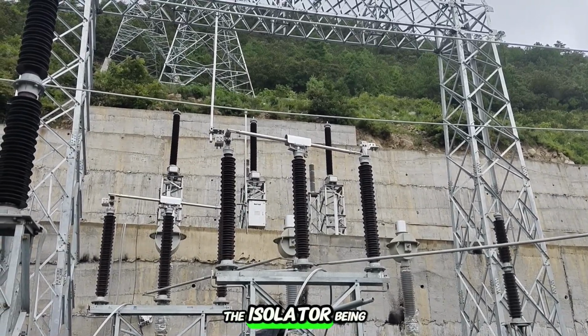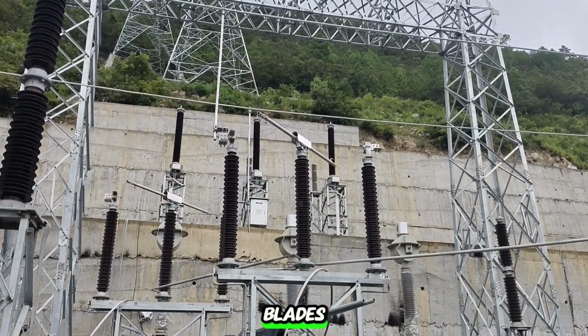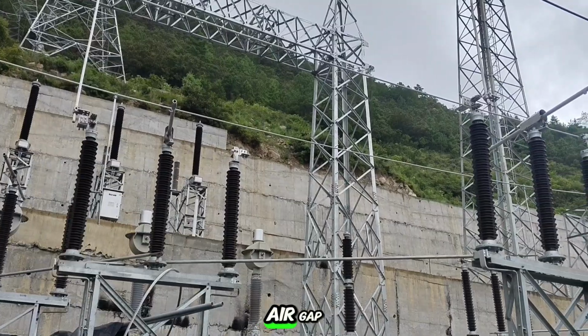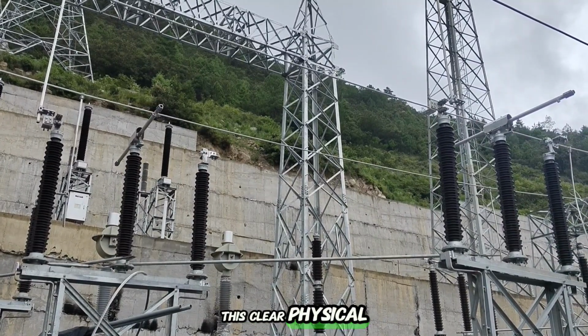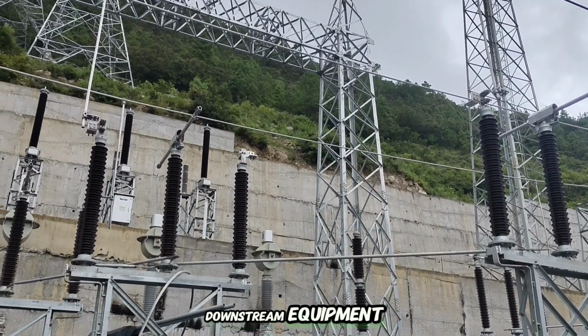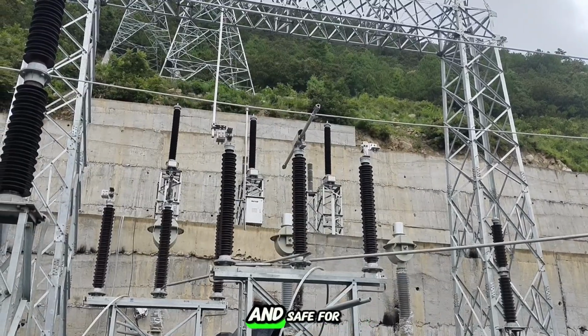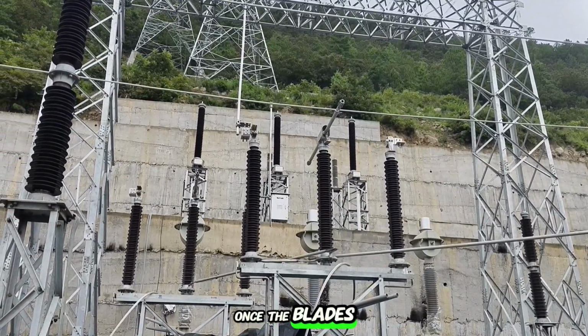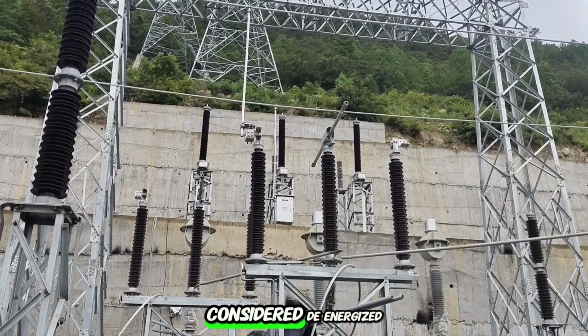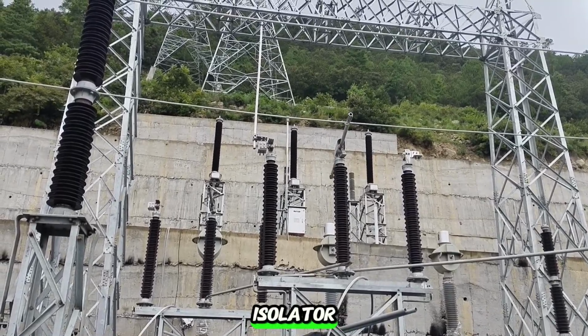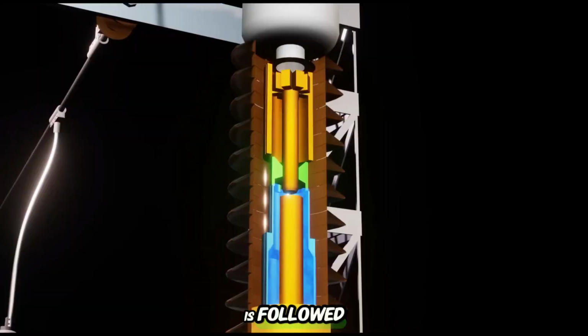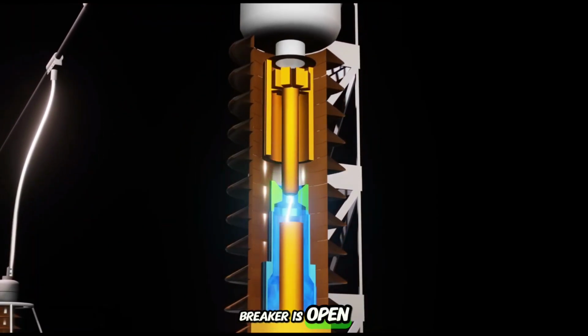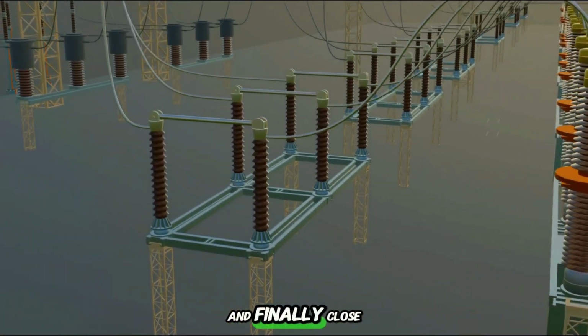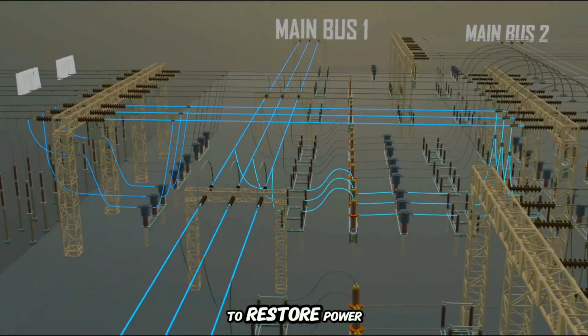Here we see the isolator being operated. Notice how the blades slowly move to create a visible air gap. This clear, physical separation confirms that the downstream equipment is truly isolated and safe for work. Once the blades are fully open, the circuit is considered de-energized. When closing the isolator, the reverse sequence is followed. Ensure the circuit breaker is open, then close the isolator blades, and finally, close the circuit breaker to restore power.